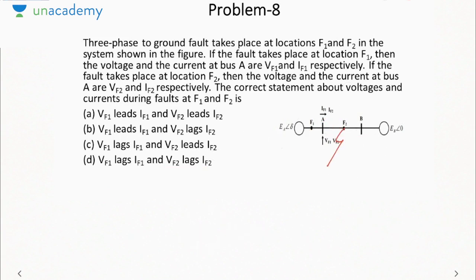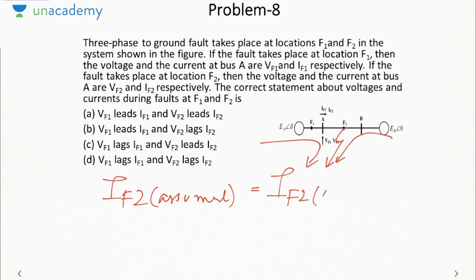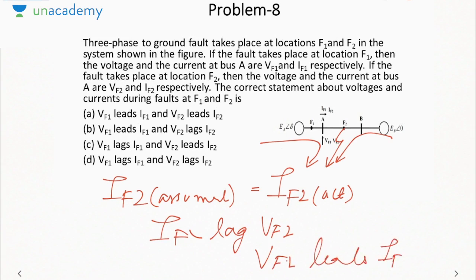Now let us take the example of a fault at F2. If the fault occurs at F2, then the current will go like this and this. So if you see at bus A, the current is going from left to right. So IF2 assumed will be the same as IF2 actual. Since both are the same, the direction is correct. Hence IF2 will lag VF2, or we can say VF2 will lead IF2. Okay. So this will be the case whenever you deal with a symmetrical short circuit fault. That is, if your assumed direction is opposite to the actual direction, then the result will be a leading power factor. If it is the same as the actual, then it will be a lagging power factor.